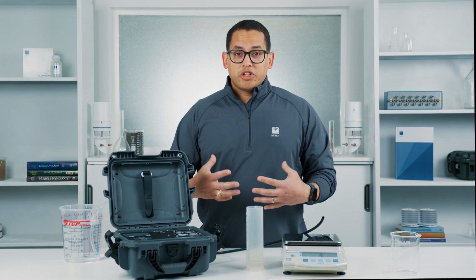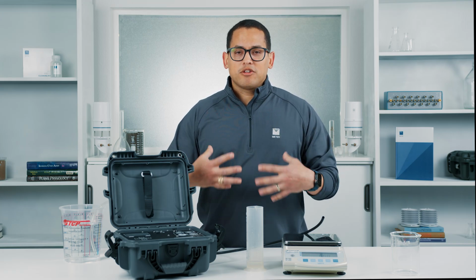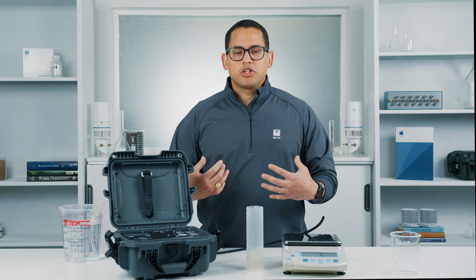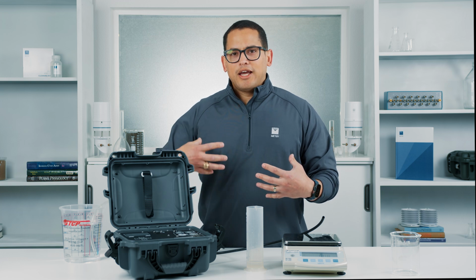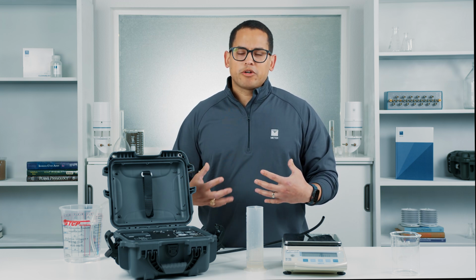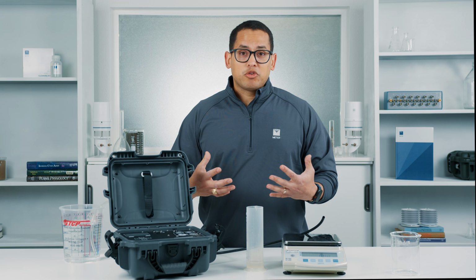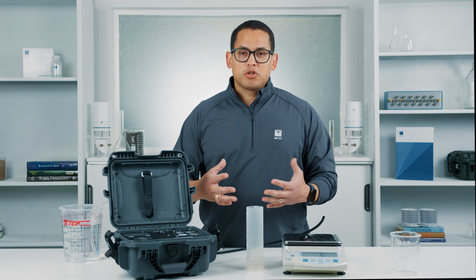Once we're done with the calibration and you hit OK, the SATURO will actually reverse the pump to clear all the water out of the lines and make sure there's no residual water remaining in the device. And we're now done with the calibration based on the volume approach with the SATURO.